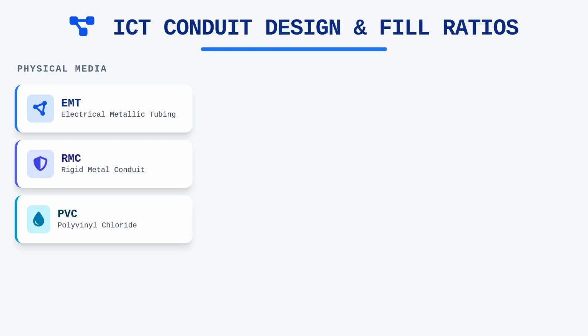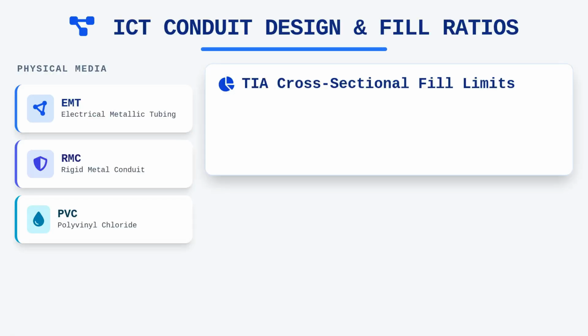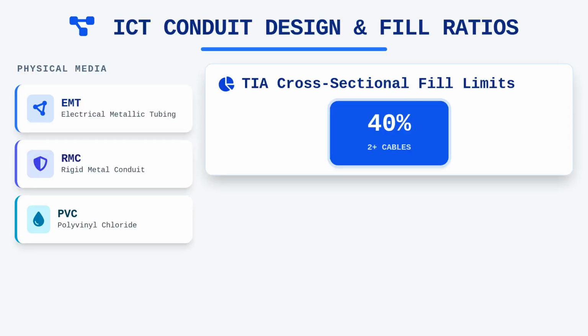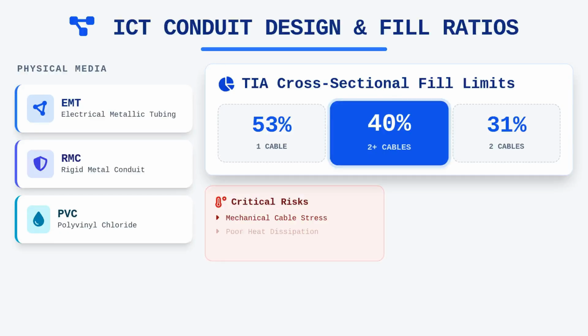The fundamental rule for any conduit system is the management of the cross-sectional fill ratio. TIA standards typically dictate a 40% fill limit for a conduit with 2 or more cables, while a single cable is restricted to 53% and 2 cables to 31%. These percentages are not arbitrary. They exist to prevent mechanical stress and to ensure that the internal heat generated by the cables is properly dissipated. When you calculate fill, you must take the outer diameter of every cable, square it, and then determine the aggregate area occupied. Failure to respect these ratios leads to difficult pulls, potential jacket damage, and non-compliance with the NEC.